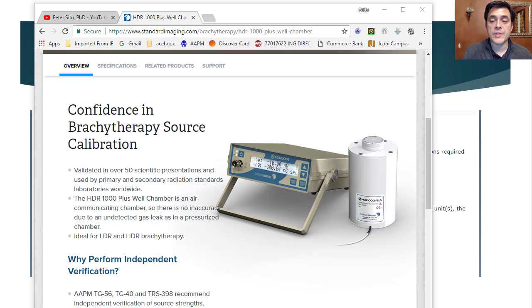Just a snapshot of the calibration system. This is an example of the standard imaging HDR 1000 Plus with the CDX 2000B electrometer, a very commonly used system for calibrating the source strength of the HDR Iridium 192.